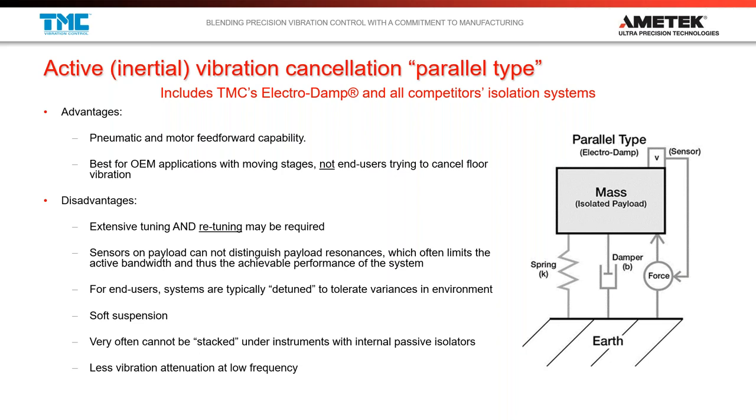If you want to get good floor vibration cancellation, you can increase your gains and make the system more and more sensitive, but there's so much input from the floor, and a lot of input from the sensor as well, that the system doesn't know what it's trying to cancel. Is it trying to cancel the floor? Is it trying to cancel the ground? So instability is always a concern with parallel type systems.